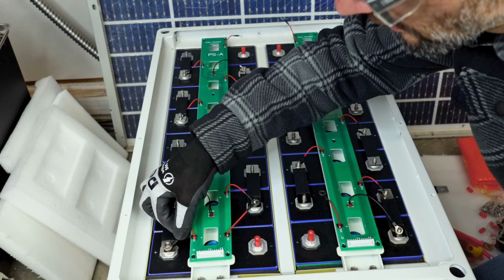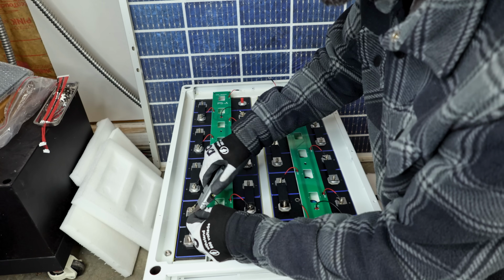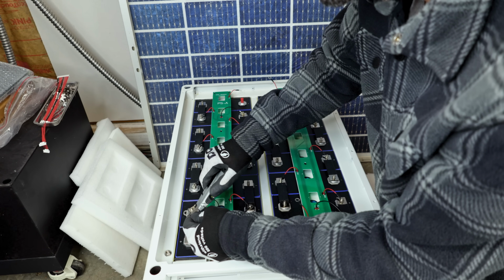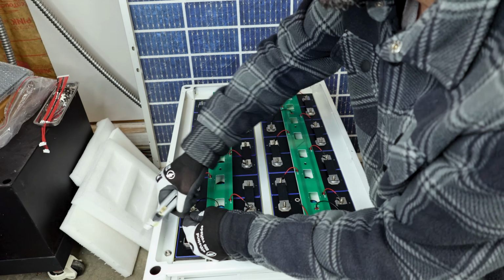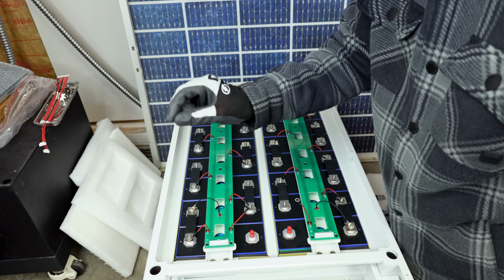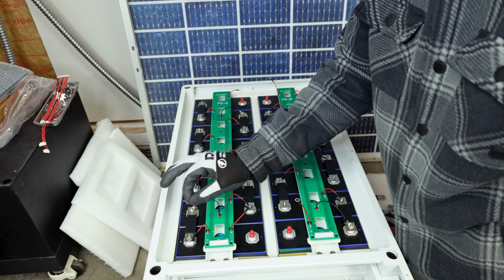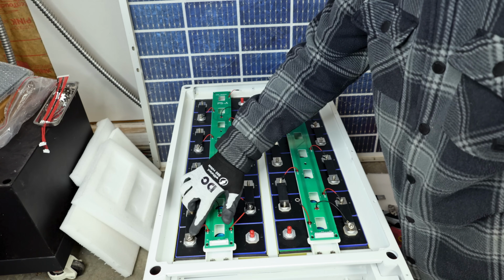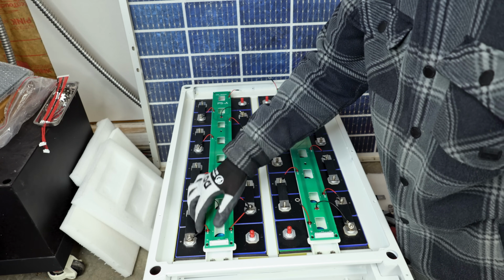If you see the nut overlapping the insulation, like I do in this case, you need to go back and remove it. If you get insulation under the nut, it won't torque properly—you'll have torque loss and the connection will get hot. You definitely don't want that.